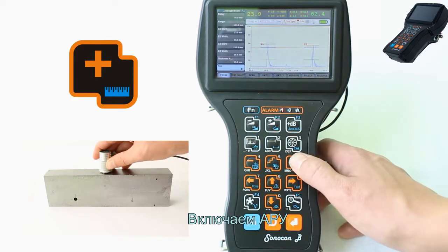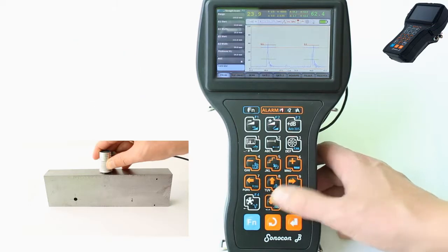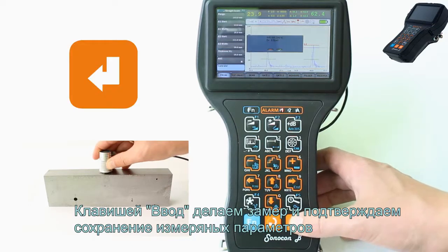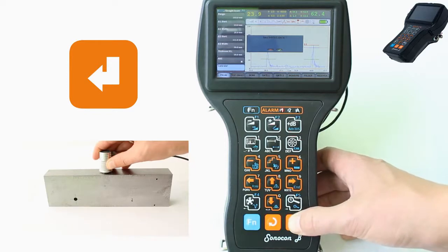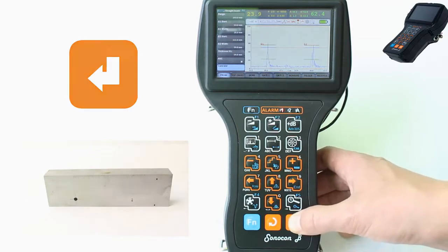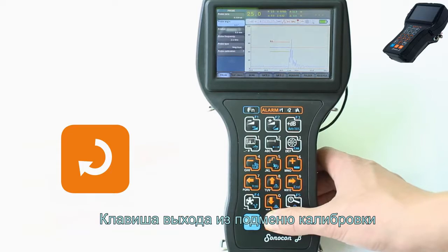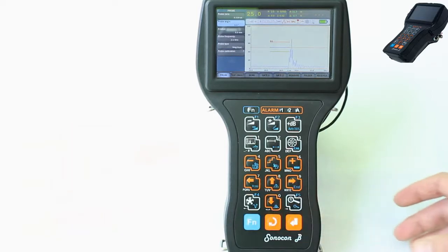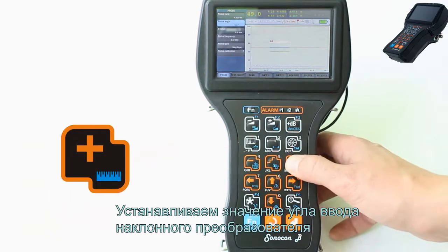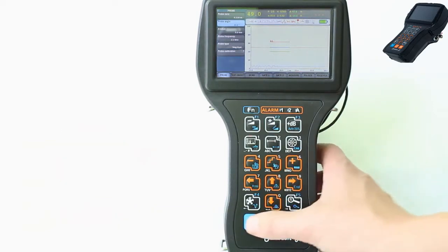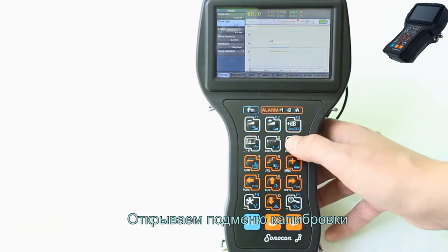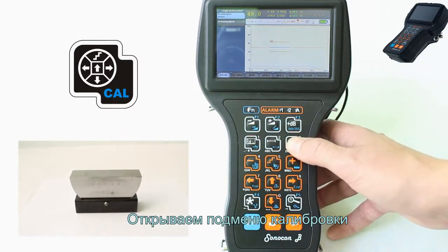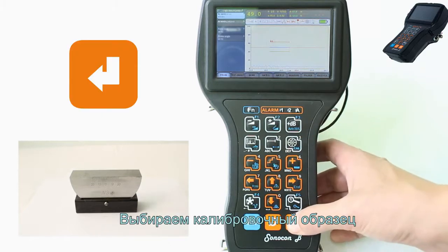Now switch on the AGC mode. Using the button Enter, we perform a measurement and confirm the saving of measured parameters. Use the Escape button to exit from the calibration submenu. Now we set up the probe angle value for the angle beam probe. Open the calibration submenu and choose the calibration block.